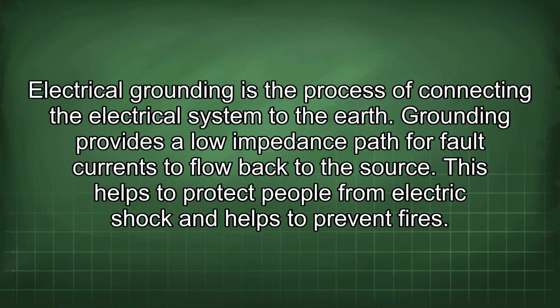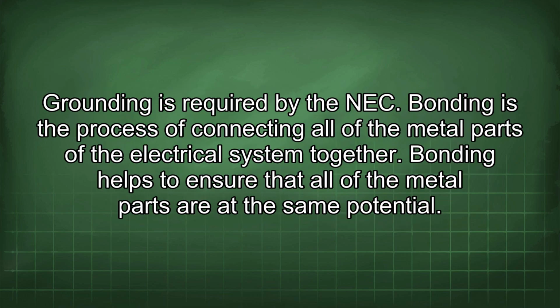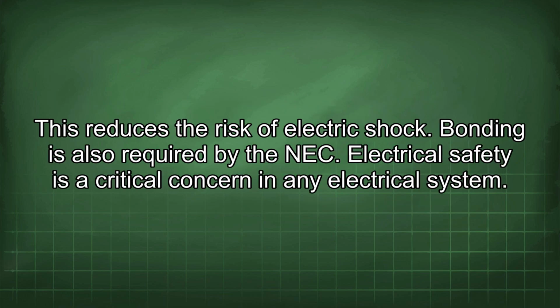Electrical grounding is the process of connecting the electrical system to the earth. Grounding provides a lower impedance path for fault currents to flow back to the source. This helps to protect people from electric shock and helps to prevent fires. Grounding is required by the NEC. Bonding is the process of connecting all of the metal parts of the electrical system together. Bonding helps to ensure that all of the metal parts are at the same potential. This reduces the risk of electric shock. Bonding is also required by the NEC.